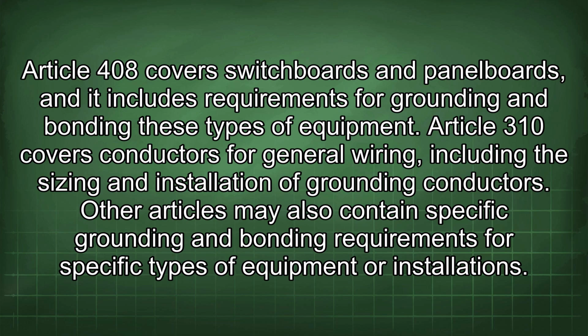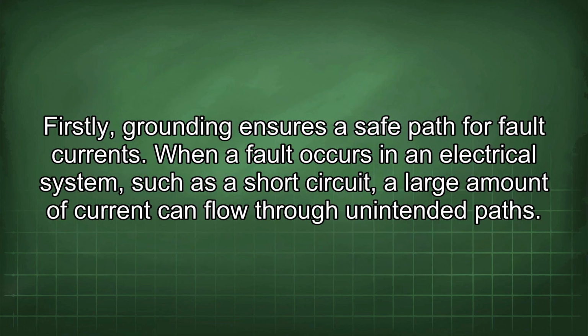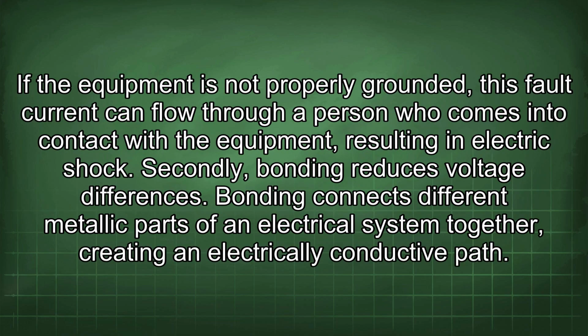Article 310 covers conductors for general wiring, including the sizing and installation of grounding conductors. Other articles may also contain specific grounding and bonding requirements for specific types of equipment or installations. Firstly, grounding ensures a safe path for fault currents. When a fault occurs in an electrical system, such as a short circuit, a large amount of current can flow through unintended paths. If the equipment is not properly grounded, this fault current can flow through a person who comes into contact with the equipment, resulting in electric shock.